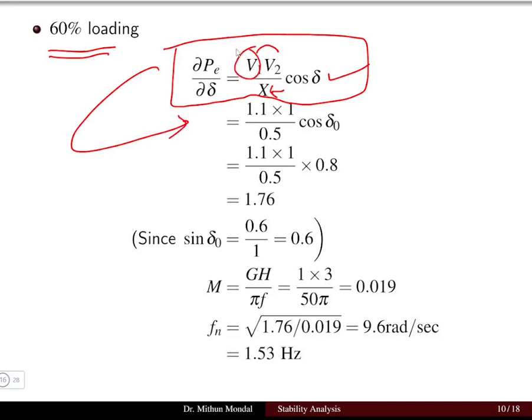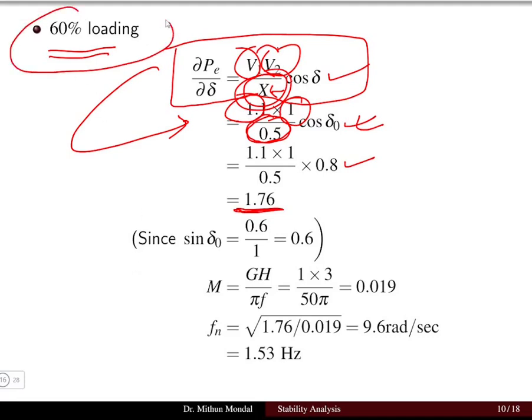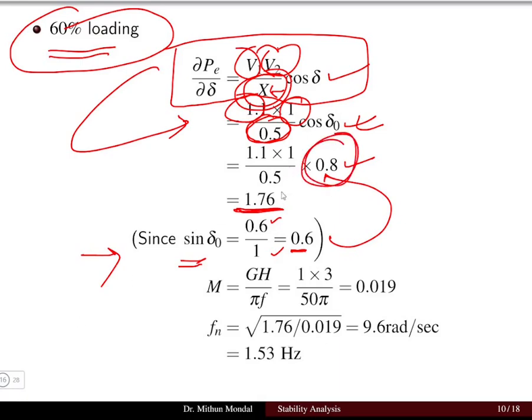For 60 percent loading: V₁ = 1.1, V₂ = 1.0, total reactance = 0.3 + 0.2 = 0.5 pu. Since the loading is 60% of maximum, sin δ₀ = 0.6, giving cos δ₀ = 0.8. Therefore dPe/dδ = (1.1 × 1.0 / 0.5) × 0.8 = 1.76. The value of M = GH / (πf) is calculated as 0.019.